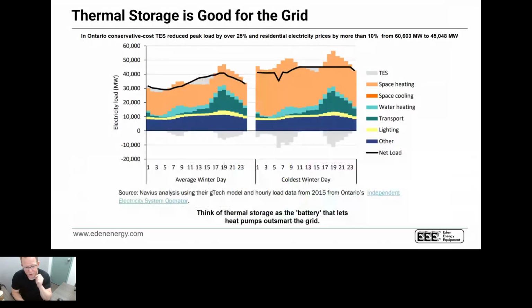And this is the last thing I want to touch on. And that is where air-to-waters are really, really cool: their thermal storage capabilities. So if you look at a radiant floor heating system right now, if you put a boiler on a radiant floor heating system, it doesn't matter when you use that gas. The really cool thing is, if you're the IESO and you're looking at, hey, what technology do we want? You 100% want an air-to-water heat pump or a water-to-water heat pump. And there's a really easy reason why.